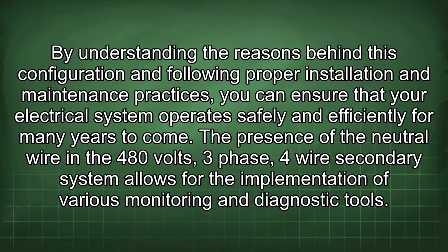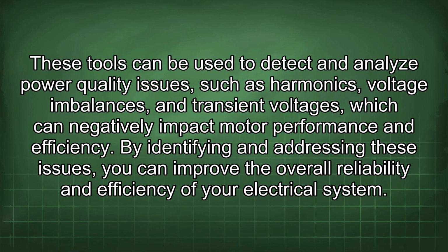The presence of the neutral wire in the 480 volts 3-phase 4-wire secondary system allows for the implementation of various monitoring and diagnostic tools. These tools can be used to detect and analyze power quality issues such as harmonics, voltage imbalances, and transient voltages, which can negatively impact motor performance and efficiency. By identifying and addressing these issues, you can improve the overall reliability and efficiency of your electrical system.